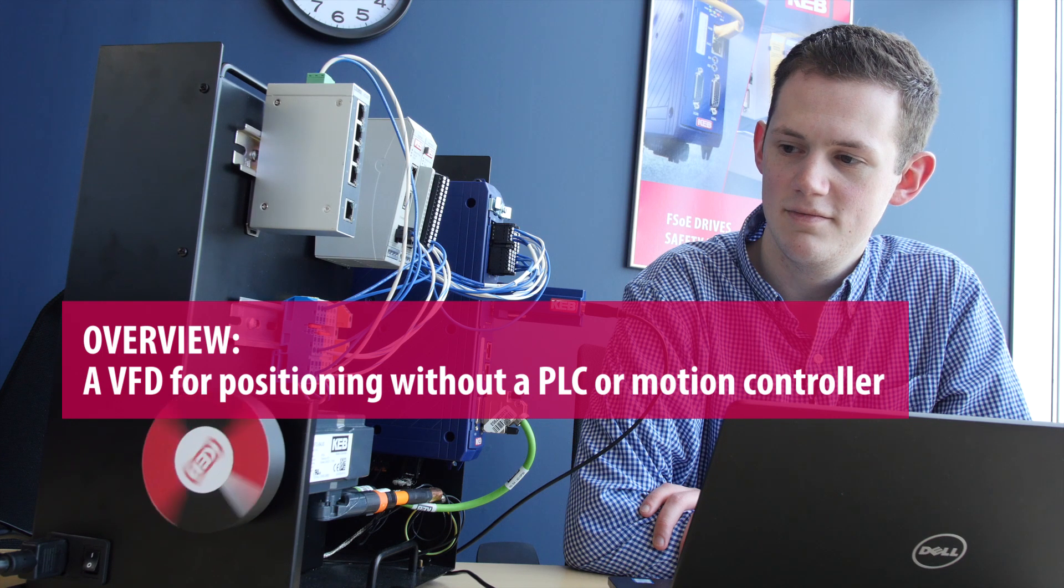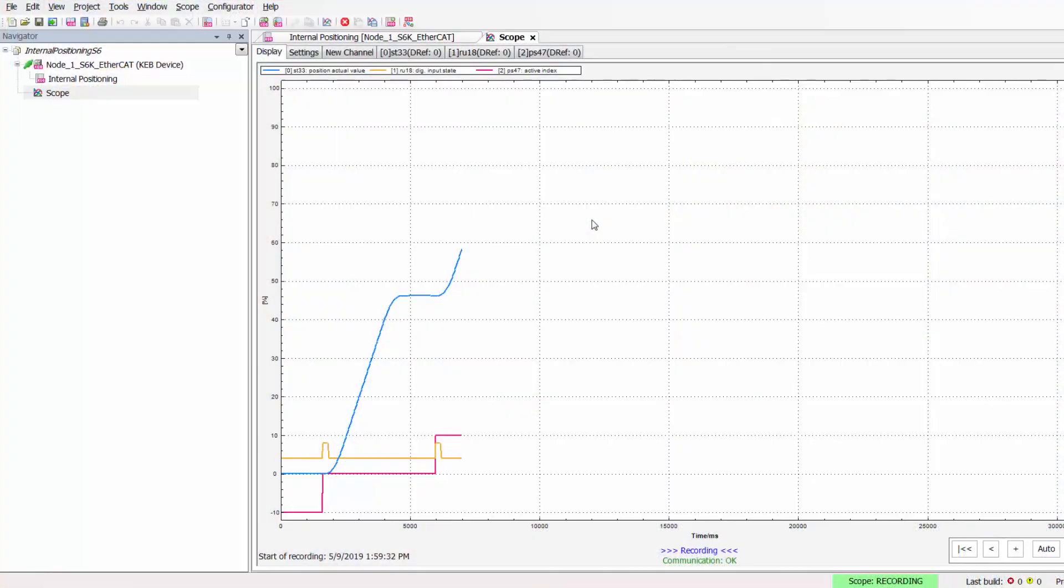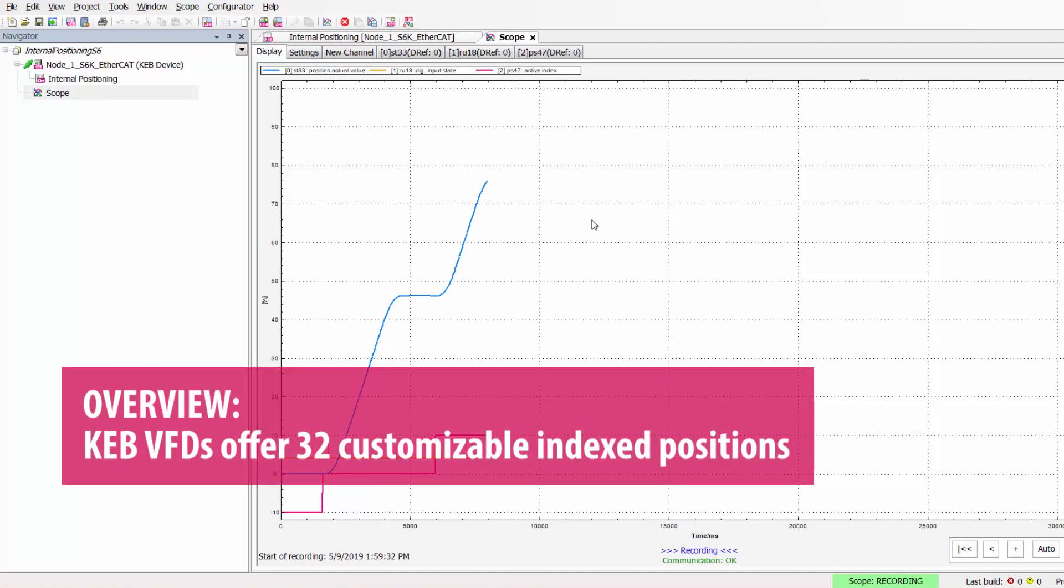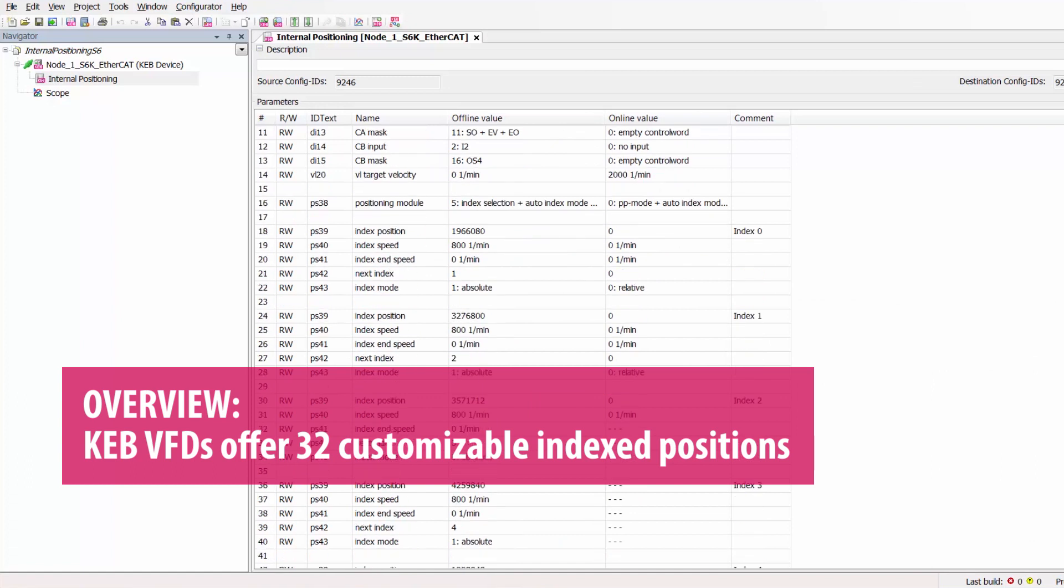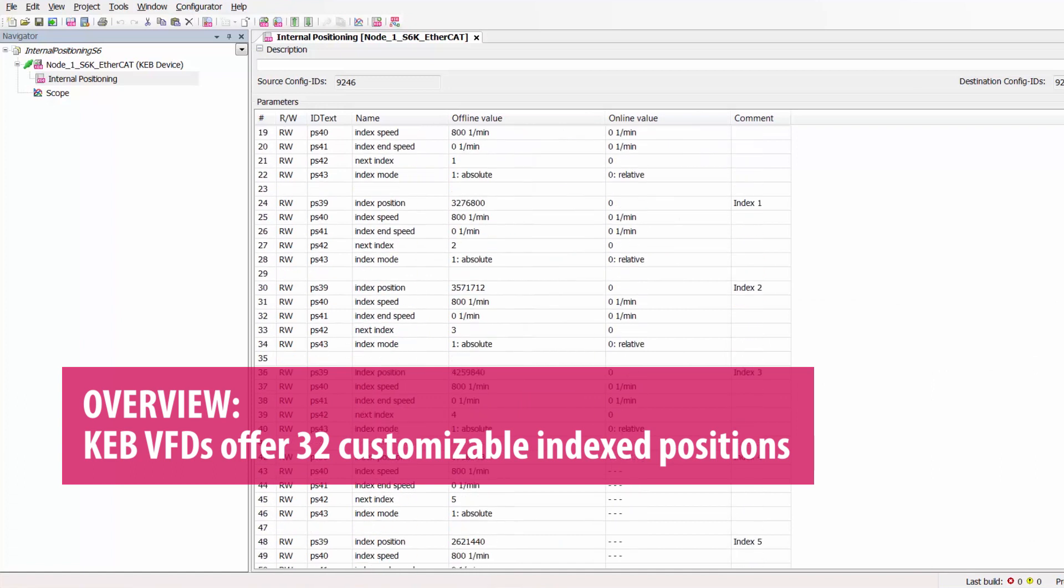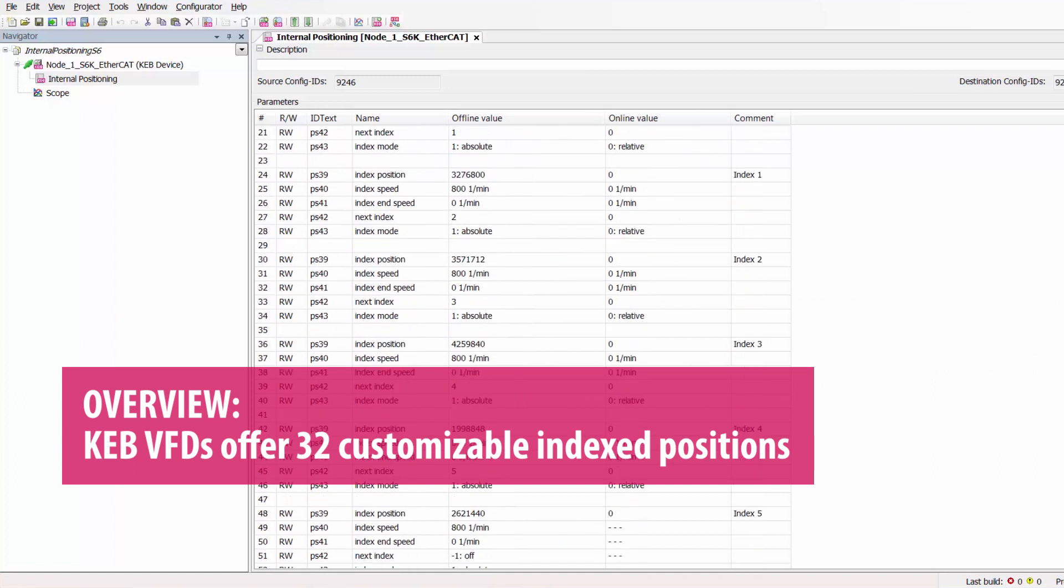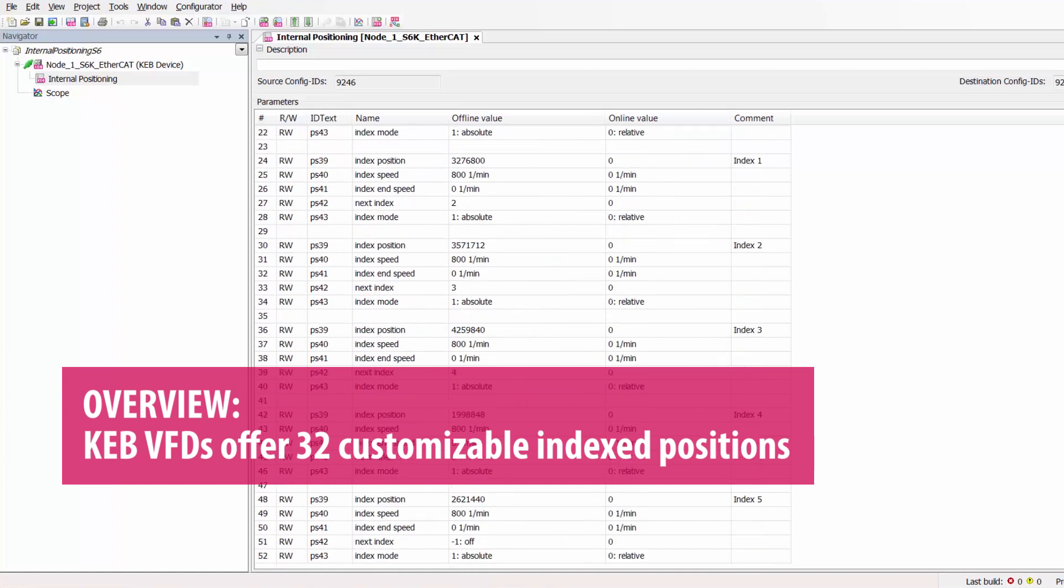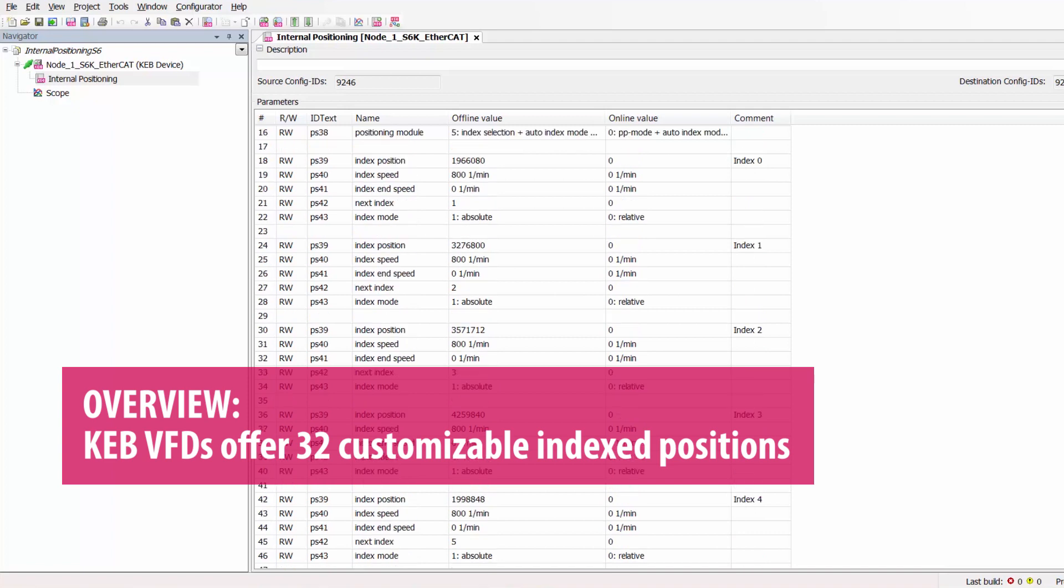So how is it used? Inside every closed-loop drive from KEB is the capability to program up to 32 indexable positions within the drive. And for each of those positions you have the opportunity to customize a set speed and positioning modes such as relative or absolute positioning within each of those indexes.